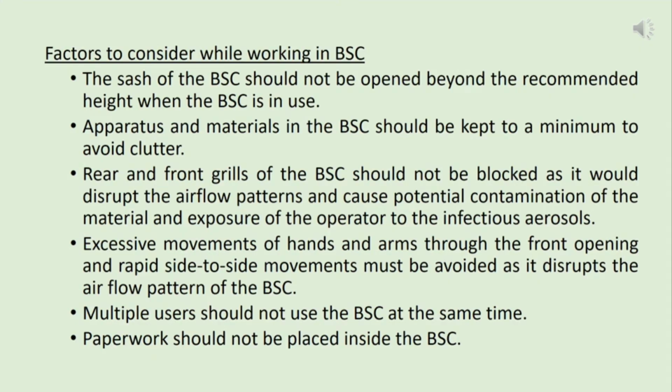Then when you're working in a BSC, you shouldn't have excessive movements of hands and arms through the front opening, and should avoid rapid side-to-side movements, because this can also disrupt the airflow patterns of the BSC. Multiple users should not use the BSC at the same time. Usually we recommend only one person work in the biosafety cabinet at one time. If you have multiple users, that means more hand movements and may also lead to cross contamination between samples.